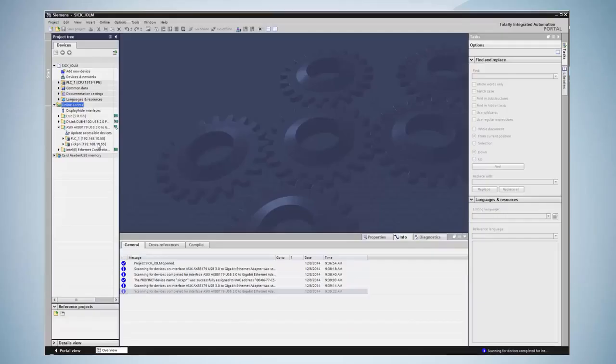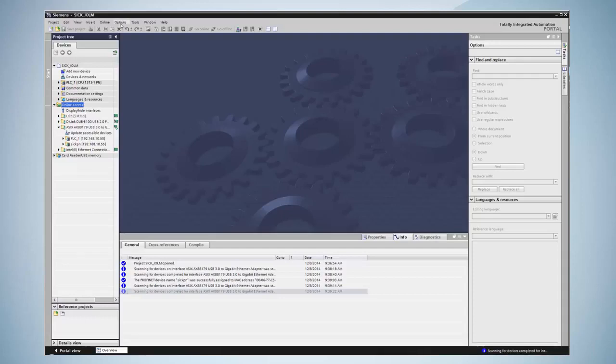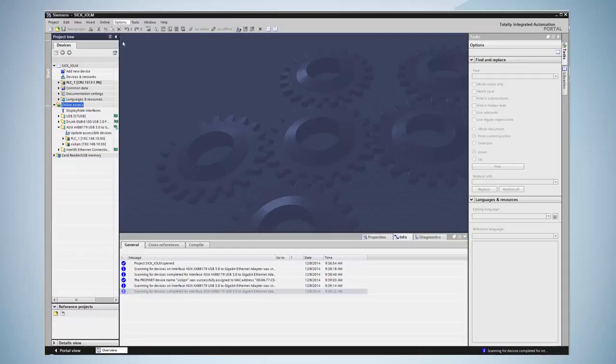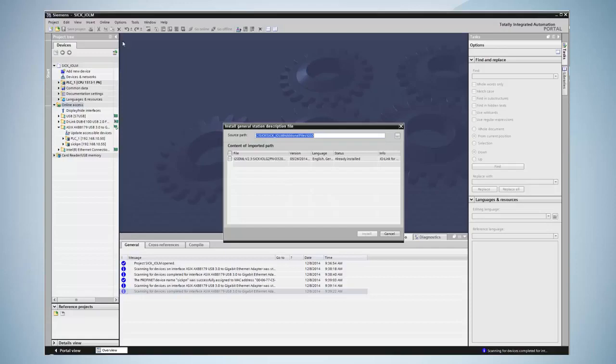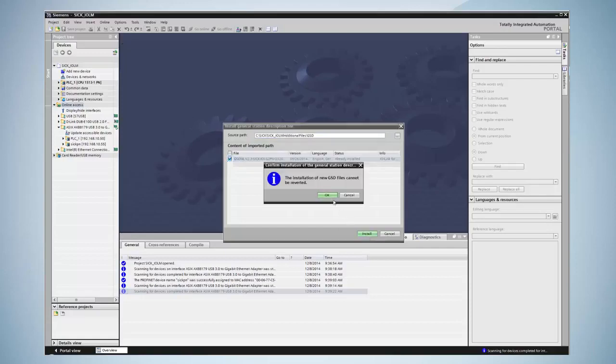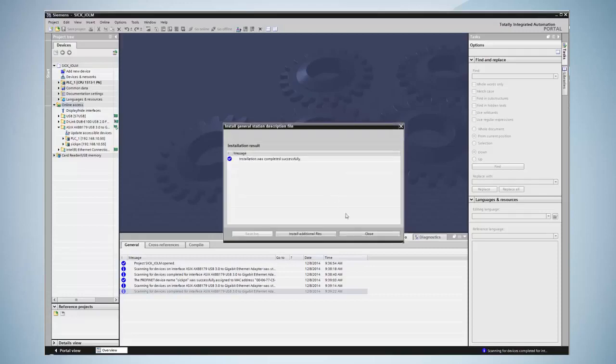The next step is the installation of the GSD file. The GSD file can be downloaded from SICK.com. By clicking on options, install general station description, the GSD file can be installed. Only after installing the GSD file is it possible to configure the PROFINET device.